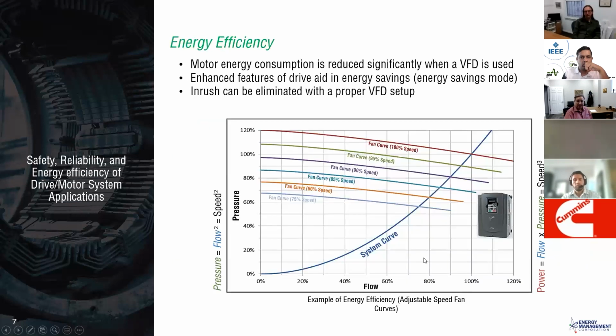And then the last one, I don't think I need to speak too much about energy efficiency. Everyone nowadays specifies drives in any kind of flow types of loads, knowing that following the affinity laws, the power is going to be reduced by the cube of the speed as you change the pump curve or the fan curve. So that's pretty well known nowadays. But if there are any questions on those, we can address those later.